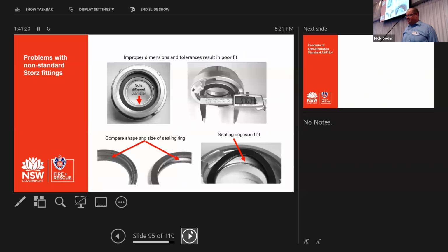When you don't have a standardised Storz fitting, you'll find dimensions are slightly out, which will affect the flow of the Storz fitting. And you'll also see that things like the shape and size of the sealing rings will differ as well. This one's actually a big one for Fire Rescue New South Wales because we have spare sealing rings in our adapter kits on our trucks. So if we encounter a fire hydrant valve without a sealing ring, we need to be able to put ours in and get to work. But if it's a non-standard Storz fitting, we can't do that.